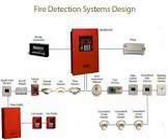The reason for this one is so that our detector does not give a false alarm, because we know that in cold countries the temperature is sub zero, and if a ship comes from a Scandinavian country to the Middle East, the temperature is close to 50, so there is a big high rise in the temperature that will also expand this one and give an alarm, right? So that's why this bleed hole is there. It will take 12 days from Scandinavia to come to the Middle East, kind of, right? And gradually the pressure will rise, expansion will happen, and gradually that will be bled out. So there will be no excessive pressure inside.